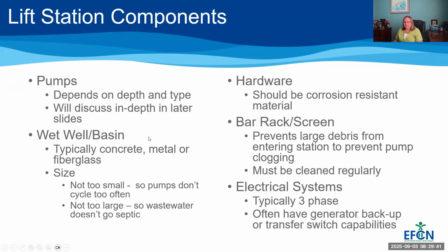The size for the basin, well, it needs to be not too small so the pumps don't cycle too often, and not too large so the wastewater isn't sitting there for hours and hours and hours and it can go septic. We definitely don't want septic water to be pumping into our manholes and then to our treatment plant. So the size is based on the amount of flow predicted, planned to enter that lift station. And that depends on how many homes are connected to that piece of collection pipe, how many businesses, those kinds of things. So flow rate dependent is how it's sized.